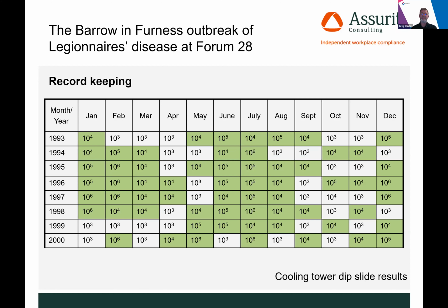If we take it one stage further, these counts of 10 to the 5 or above mean you're looking at 100,000 colony forming units of bacteria per millilitre of water, so a fifth of a teaspoon. If you factor that up to the size of a typical cooling system, where you're looking at tens if not hundreds or thousands of litres, that is a lot of microbiological burden. This is when the system was effectively out of control by indication.